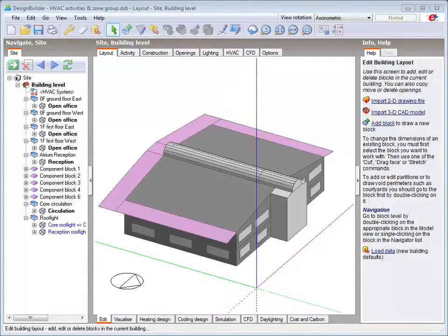The zone group concept enables a simplified HVAC schematic representation, as only one set of equipment and connections needs to be defined for the group, while still enabling you to change equipment properties for individual zones, such as terminal unit ratings or efficiencies. To assign a zone group or groups, I go to the HVAC system in the navigation panel.